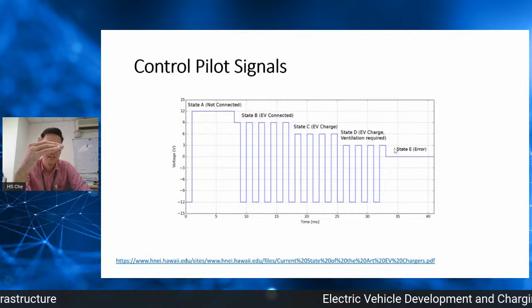Once you plug the EV into the charger, the voltage turns into a 1 kilohertz pulse with magnitude plus 9 volt, minus 12 volt. Once the EV starts to charge, the level changes from plus 9/minus 12 to plus 6/minus 12. When the EV requires ventilation—because the battery is heating up—the level changes to plus 3/minus 12. If there's an error on the car, the voltage completely collapses to 0. By looking at this voltage level, the EV charger can know the status of the connection: charging, not charging, ventilation, not ventilation, or an error with the car.